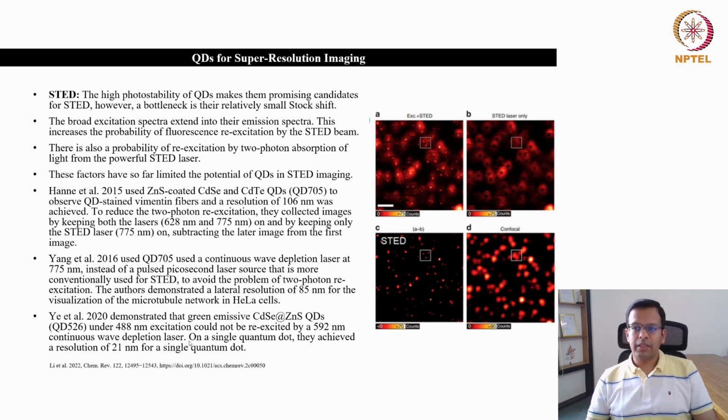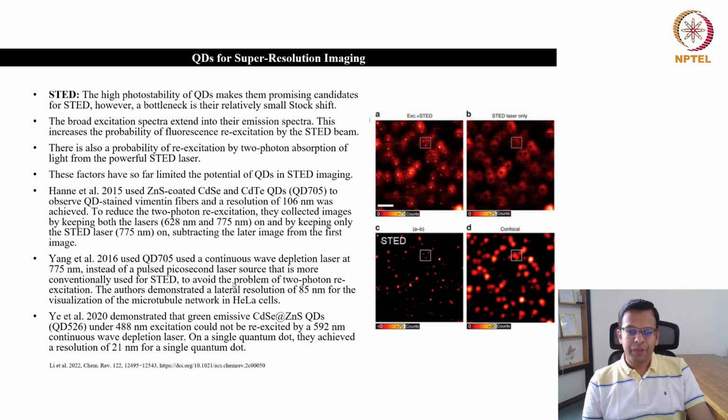So instead of using quantum dots in the red range, they used quantum dots which are green emissive, under 488 nanometer excitation, with a 592 nanometer depletion laser, and that is a continuous wave depletion laser, not the pulsed picosecond traditional laser generally used for STED imaging.